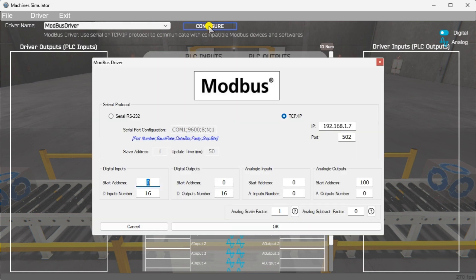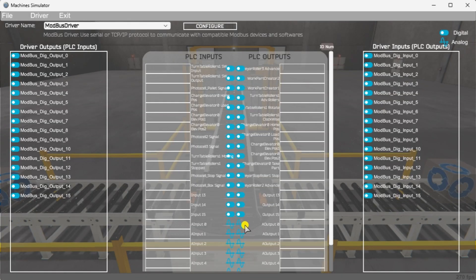Select the Configure button. We can now enter the information for our Modbus driver. Select TCP IP — this means the Ethernet port on the computer will communicate to the DoMore PLC simulator. The digital inputs from MS to the DoMore PLC will be MC1 to MC16, starting at address 0 due to the offset of 1. Digital outputs from MS to the DoMore PLC will be MI1 to MI16, beginning at address 0 due to the offset of 1. Select the OK button. You will now see the inputs and outputs specified for the Modbus driver. We can manually assign driver outputs to PLC inputs, but the automatic assignment works well and will save you time.